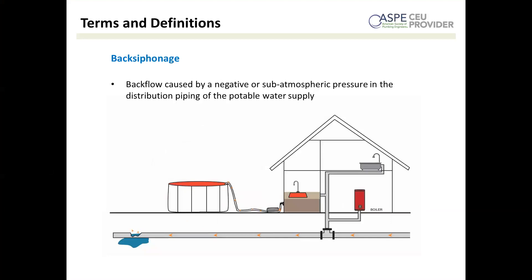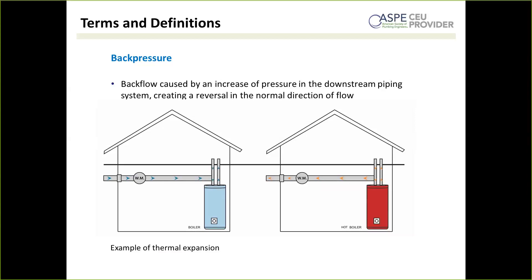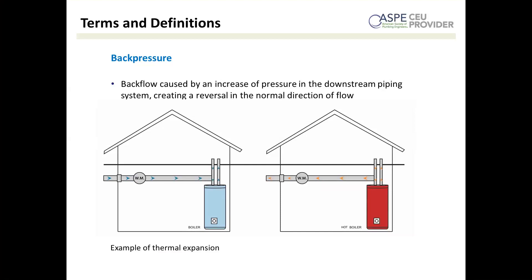You can think of back siphonage as a pull from the supply side, which leads to our next term: back pressure. Back pressure is a push from the downstream side. A back pressure condition occurs when there's an elevated pressure between the potable and the non-potable source. This can be caused by pumps that increase pressures above city water supply pressure, forcing non-potable water in the opposite direction. Also, boilers or other equipment with heat cause thermal expansion, resulting in pressures that can exceed incoming water pressure and force non-potable water into your potable piping system.